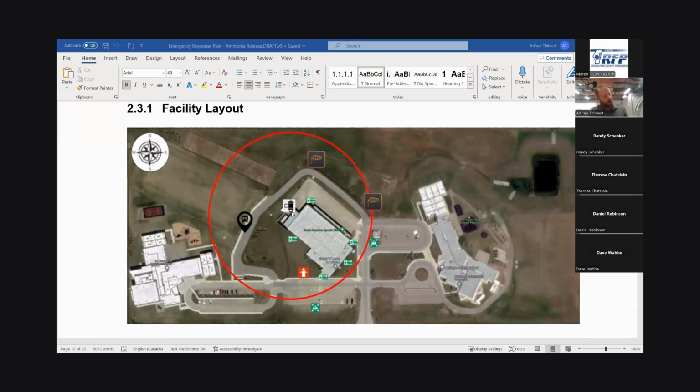300 meters, 1,000 feet is the isolation zone in all directions. Those nurse tanks are around 900 pounds, so that's what we base ours on. So talking about 60 pounds, you still probably want to have something in place, and you have to have the emergency systems as far as exhaust fans and emergency stop buttons. You still have to have that. But you're looking at less of a potential for sure.